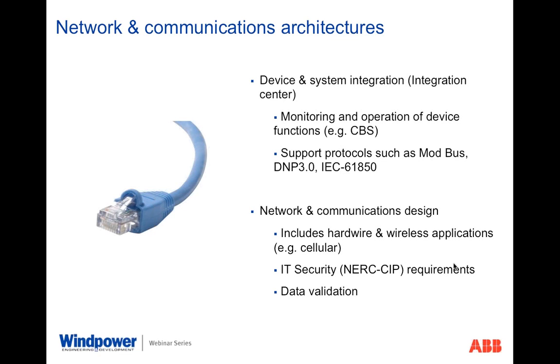Another key element associated with the communication is the validation of data being monitored, knowing the information being displayed at the asset level is correct. We do this in two separate methods. First, the ABB monitoring devices offer an integrity feature that can indicate any sensor or data issue at the breaker. The second level is done from the asset server, which continually polls a device to ensure that proper communications are not lost. Thus, an alarm will be generated and the condition will be suspended, indicating a specific area of concern. This is critical, understanding whether the data that is received by the user is accurate and appropriate.